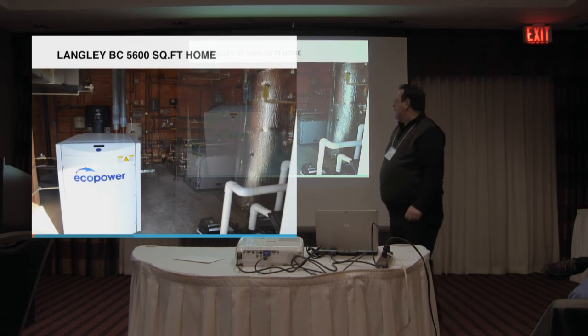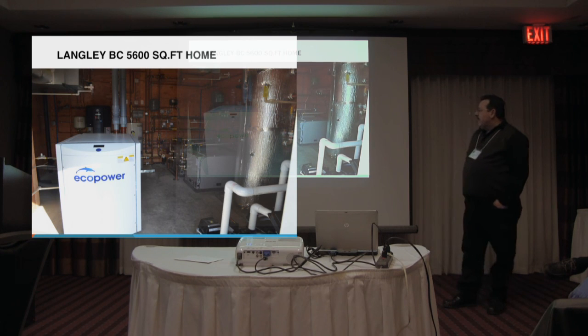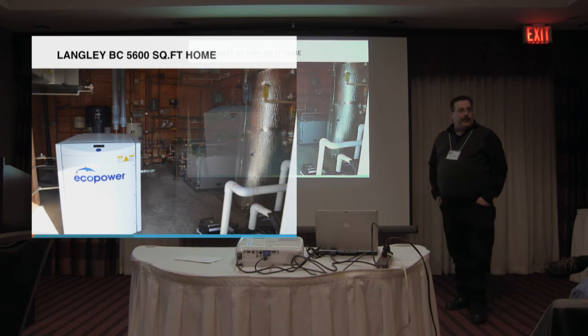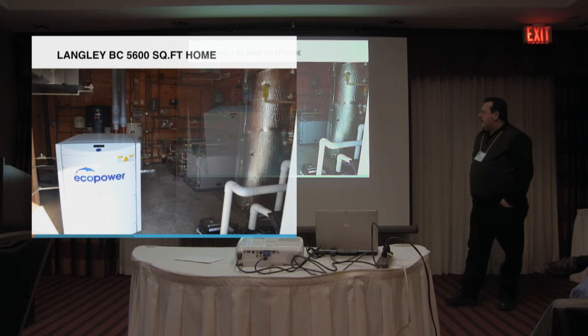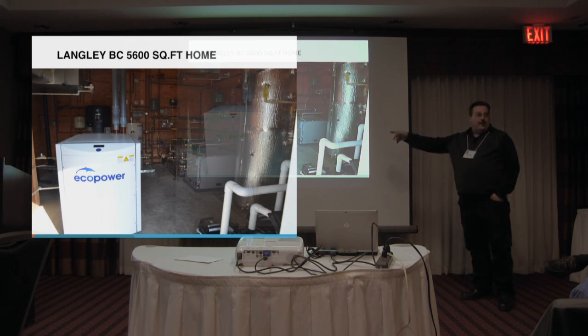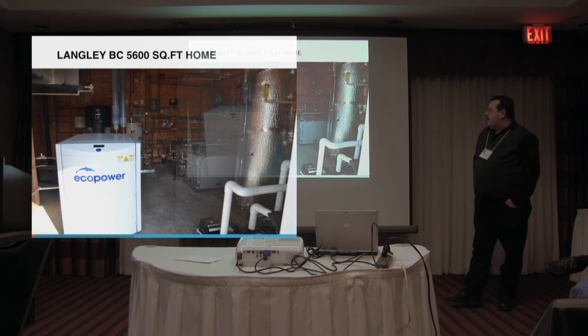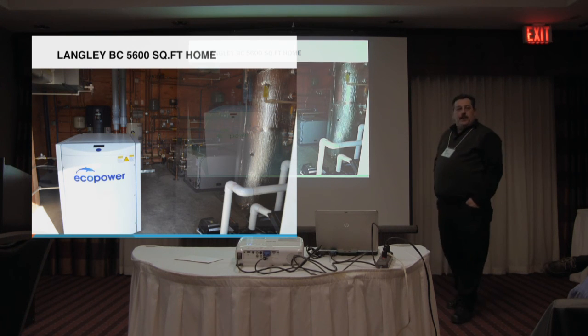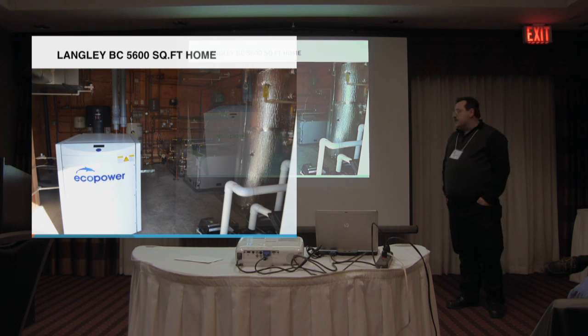So this is the mechanical room that it's installed in. And here's what's really interesting on this project: you have an EcoPower unit backed up by 2 geothermal units, 2 water-to-water units, because it's cheaper to run that EcoPower than it is to run the geothermal units. Those are on well water as well, so they've got good entering water temperature, so they're getting fairly high COPs to begin with. But the CHP, for the most part, keeps up with the load as the peak demand increases. You've got 4 stages of heat pump there that'll come on to back it up.